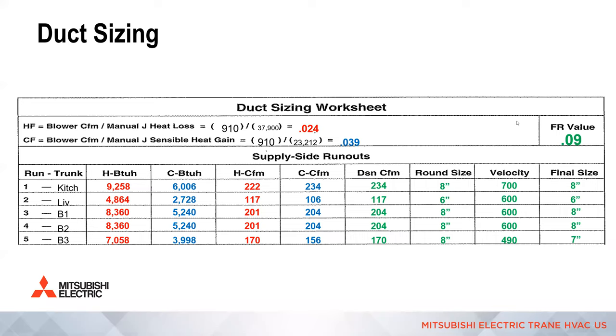Do turning vanes affect TEL positively or negatively? I did address that one. Turning vanes will reduce total equivalent length, but unfortunately in residential, it often doesn't get done right. So you can't field install that. You want to order the fitting from the shop with those vanes already installed correctly.